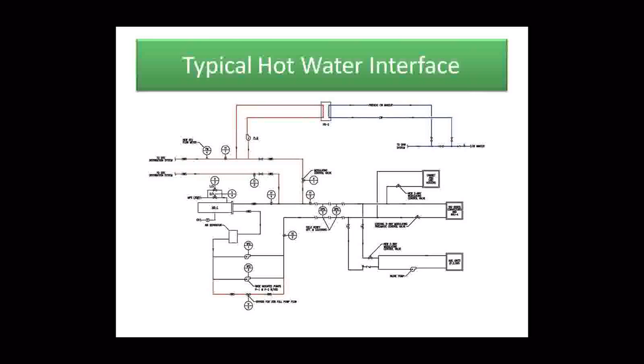The great thing about this schematic and how it would work if the geothermal system for some reason would go offline during the winter, we can simply go back to steam, and we have steam for backup to all these buildings that's there, turn it on, and we got heating by the old method of steam, in this case though produced by burning natural gas.